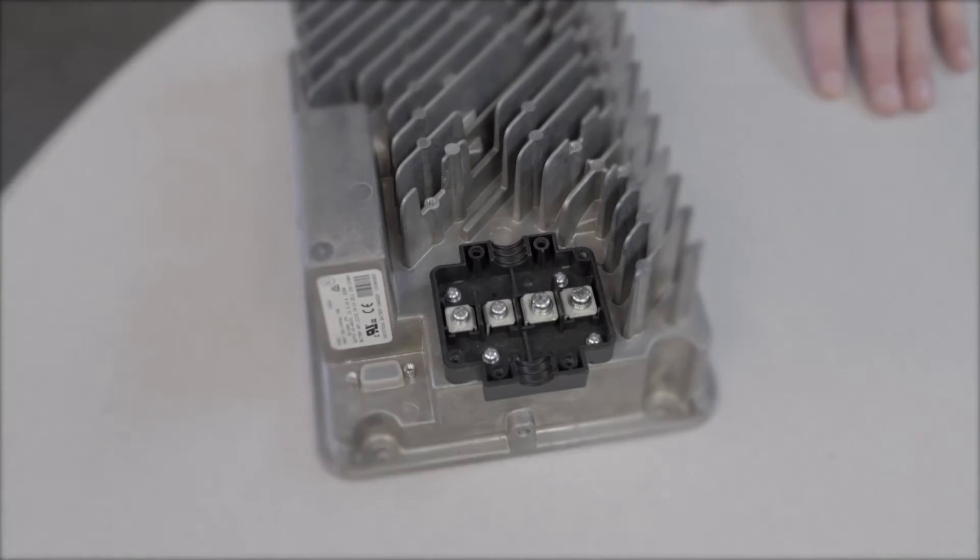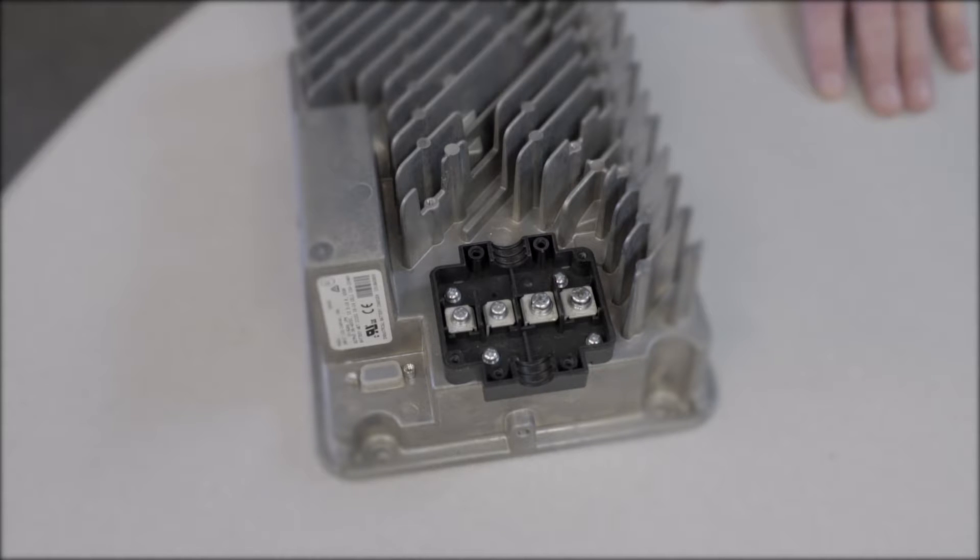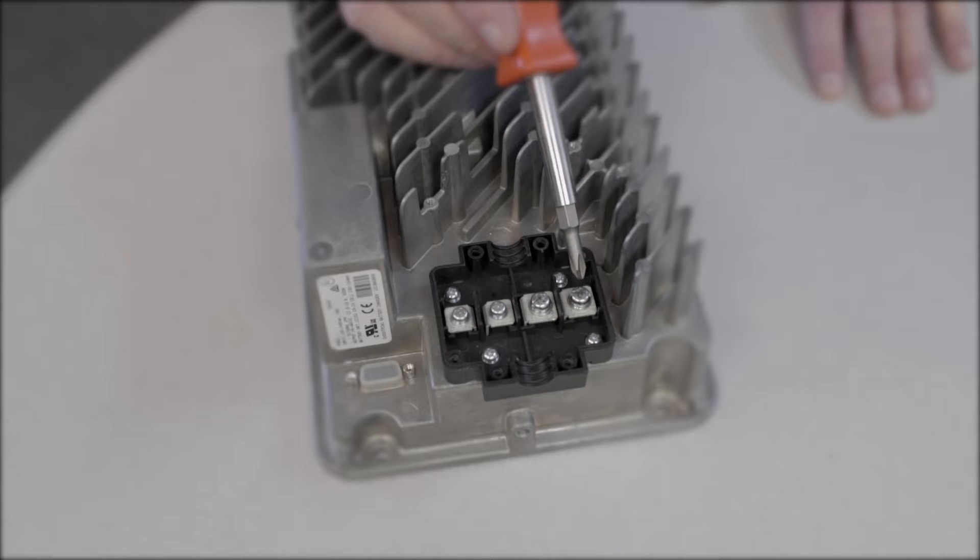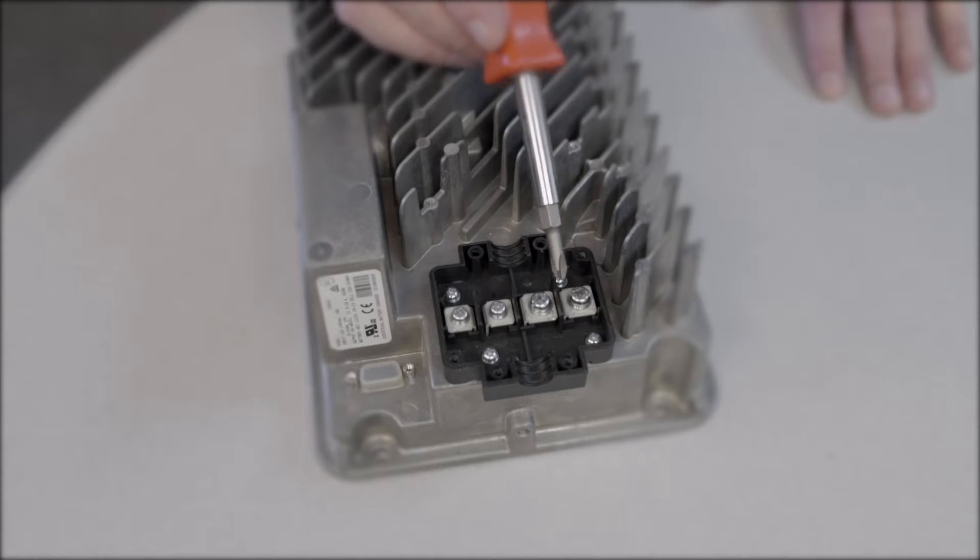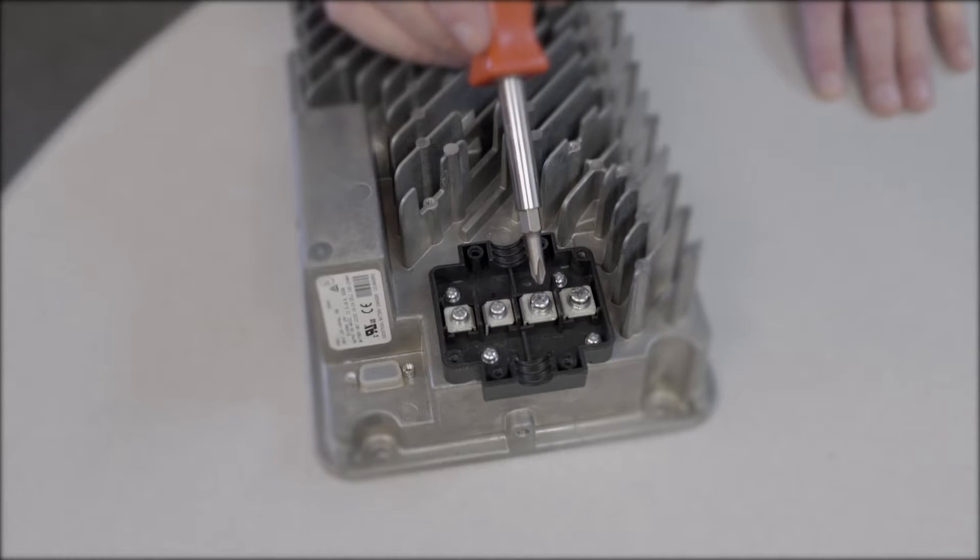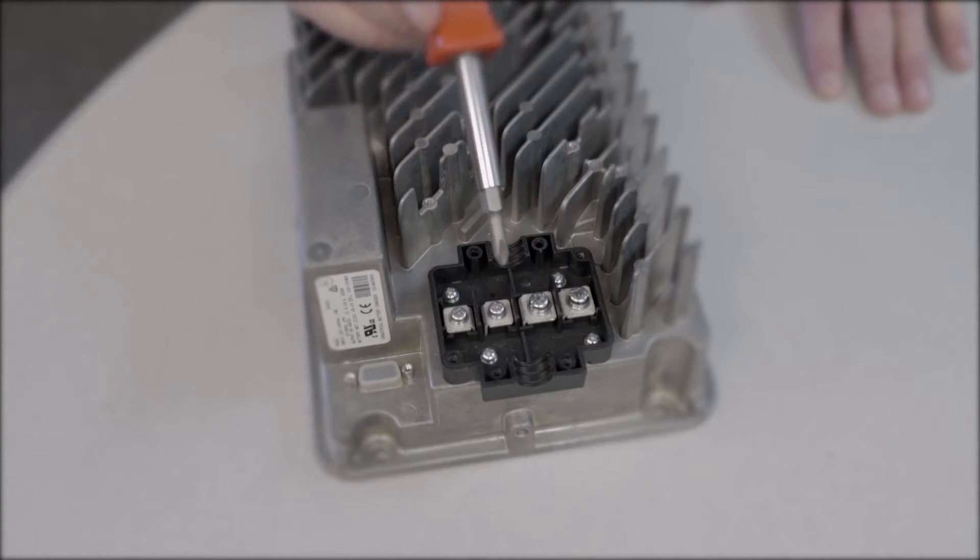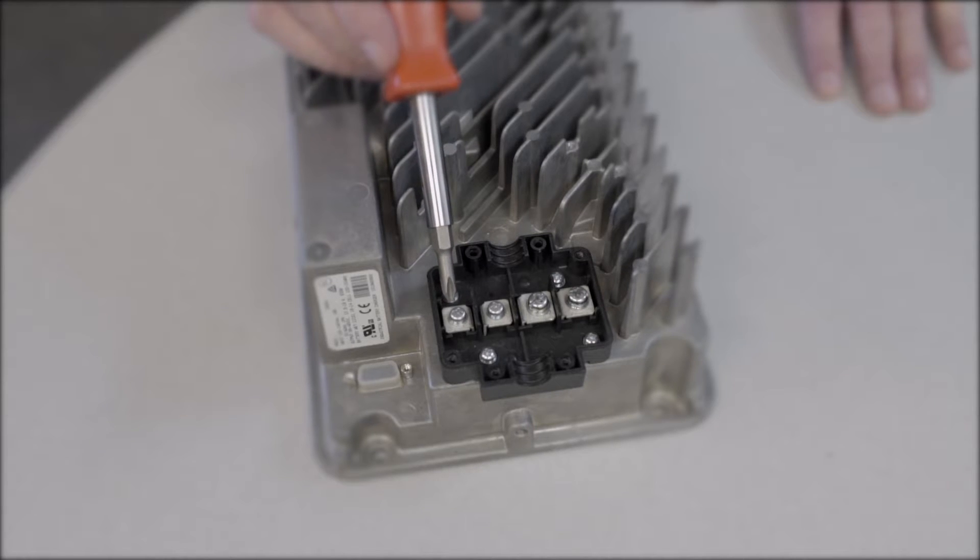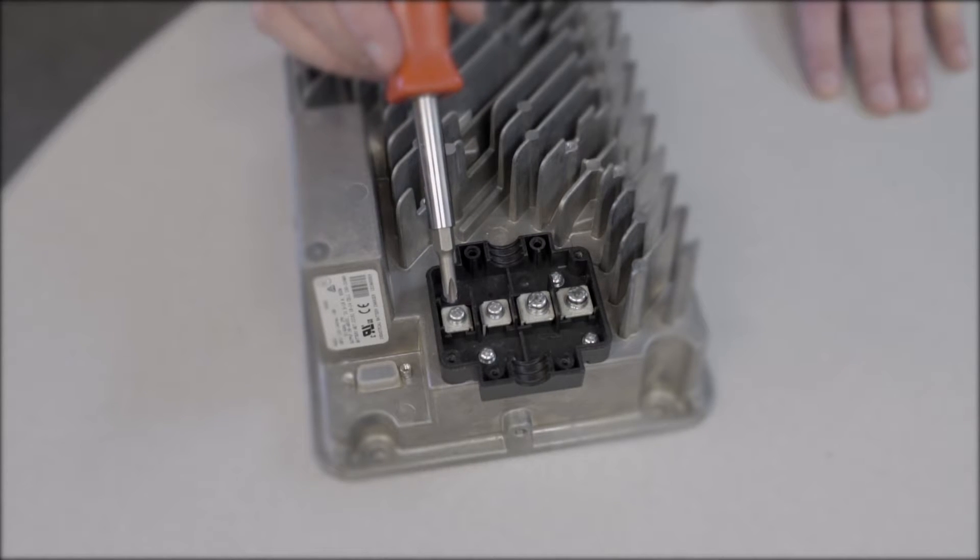The next step in the process is identifying the terminal lugs on the back side of your charger. The one closest to the edge is the positive, followed by the negative, and the other screw that you'll ever use on any installation is this number two screw for your lockout configuration.